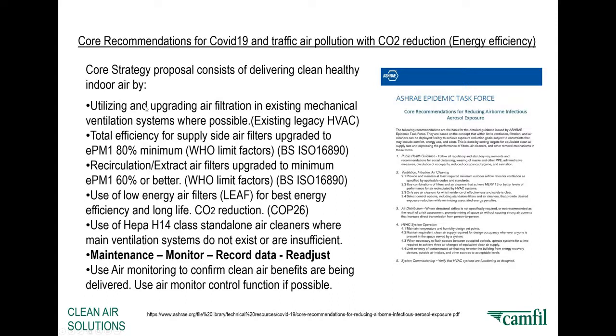So if we have a utilisation and upgrading of existing ventilation systems, improving ventilation filtration, both for supply air coming in from outside, but also recirculation, whether that's the main air system itself or standalone air cleaners or air purifiers, we can monitor the air and demonstrate effective delivery of clean air into the building. Air cleaners standalone tend to use HEPA filters, and general HVAC systems use the ISO 16890 with a high EPM1 reduction for their classifications. And I would stress that air filters need to be constantly monitored for their effectiveness.